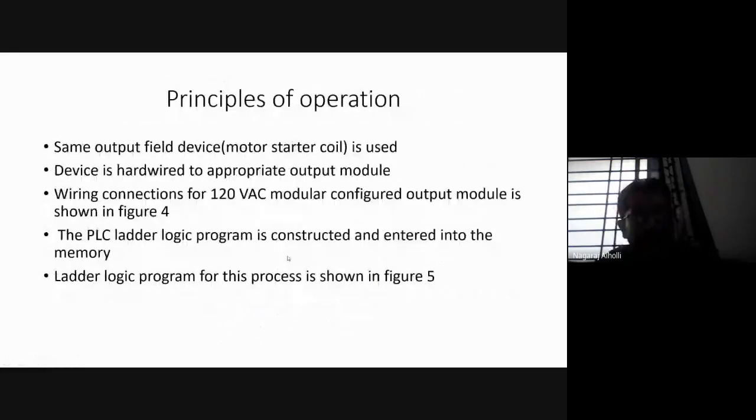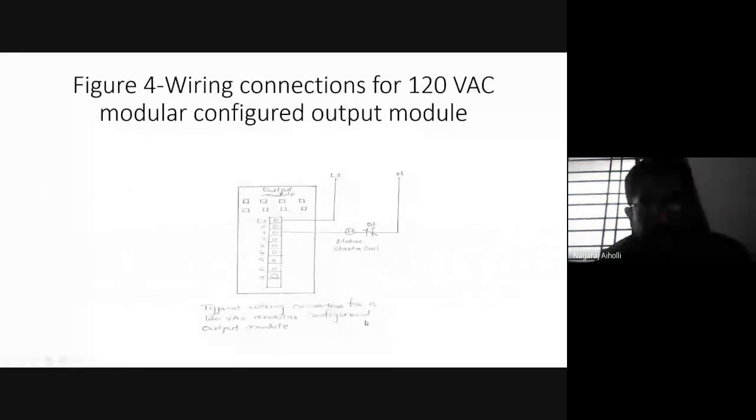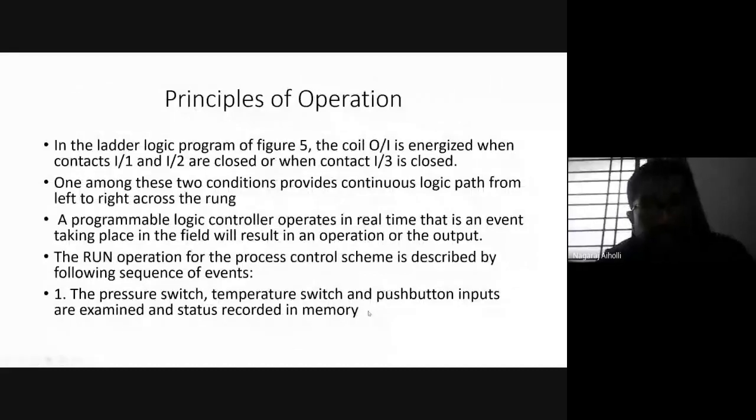Okay. During the program scan, the controller monitors the inputs, executes and changes outputs. For the program to operate, the controller is placed in the run mode. If you are placing the programmable logic controller, PLC, in the run mode, then it executes the program. In the ladder logic program of figure 5, the coil O1 is energized when contacts I1 and I2 are closed, or when contact I3 is closed. Again, the same thing. One among these two conditions provides, this is important here.